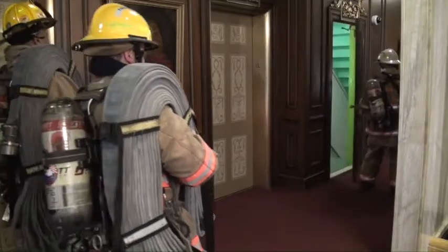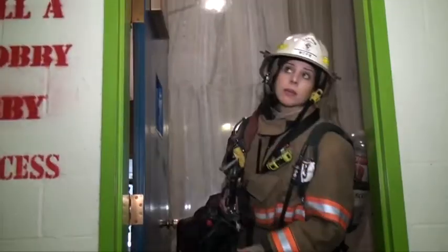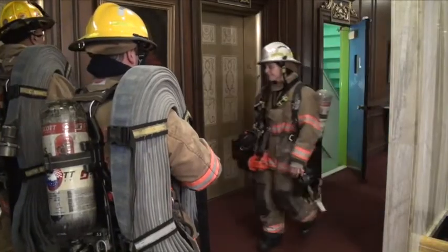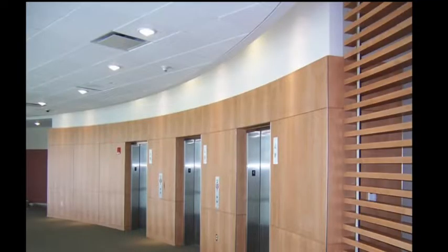Once you determine that you will be using the building's elevator, personnel must note the location of the nearest stairwell before entering the elevator. If a smoke or heat detector is activated at the predetermined floor where the elevator normally recalls to, the elevator will come to an alternate predetermined floor. It may be important to pre-plan buildings that have Phase 1 capability in order to know what predetermined floor Phase 1 will recall the elevator cars to and evaluate if Phase 2 capability exists.